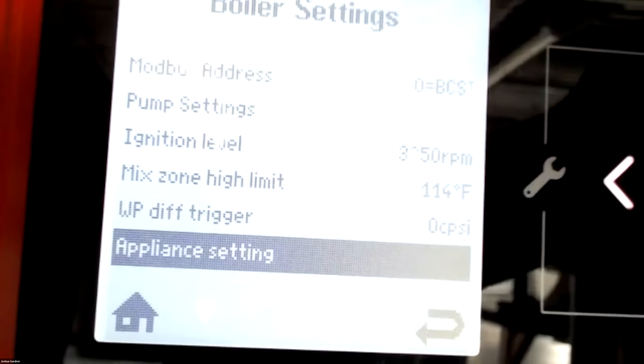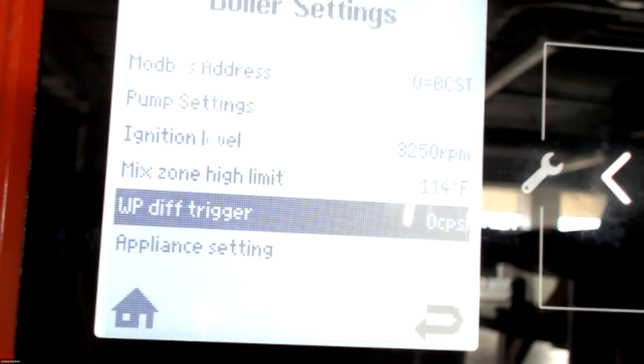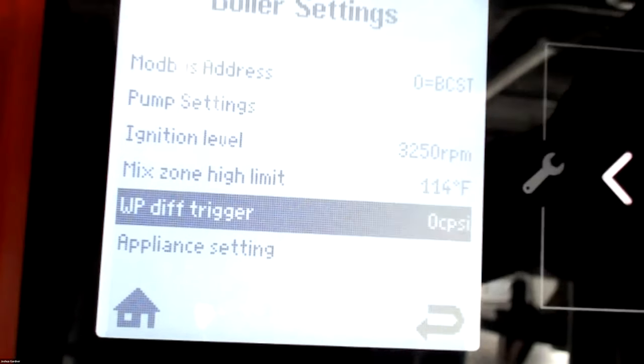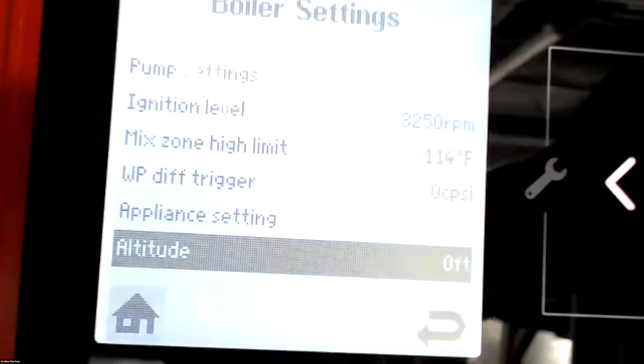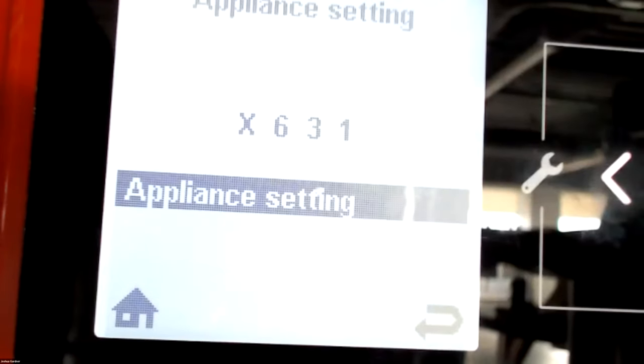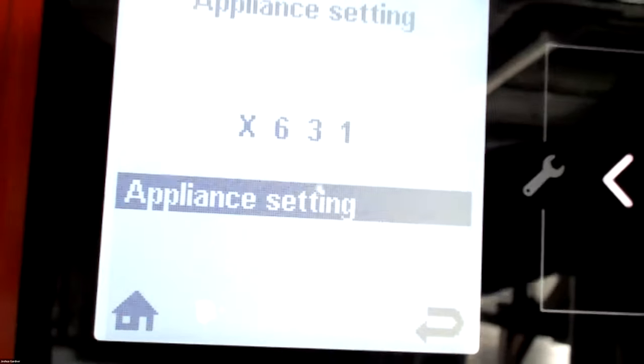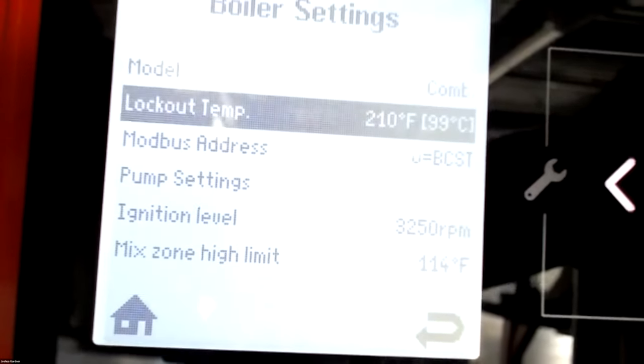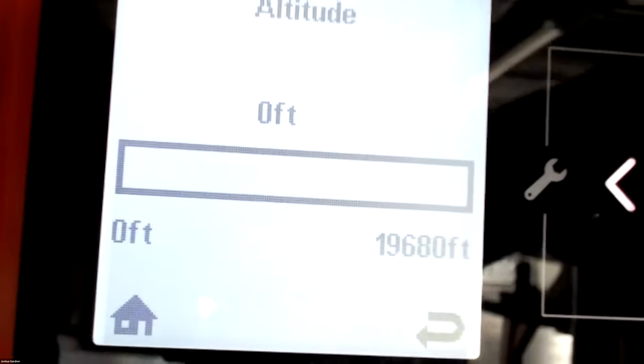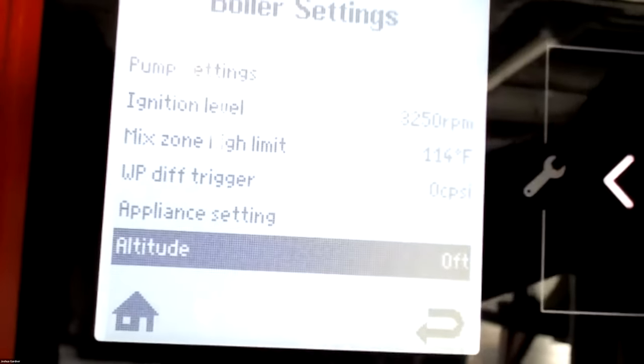The water pressure differential trigger, there's a few settings in here that we aren't using that are in some of our boilers overseas. Again, this control is very universal in a lot of our equipment, but that WP differential trigger we do not use, not active. And our appliance setting, altitude. So the appliance setting, this is where we set the boiler to what that sticker says. So if it's a propane combi, this is where we go and adjust that setting. And then obviously altitude. If we need to change the altitude of where the boiler is being installed, this is where we can adjust that. And those are the boiler settings.